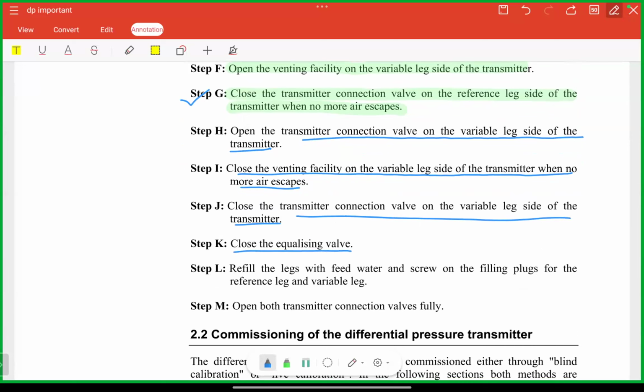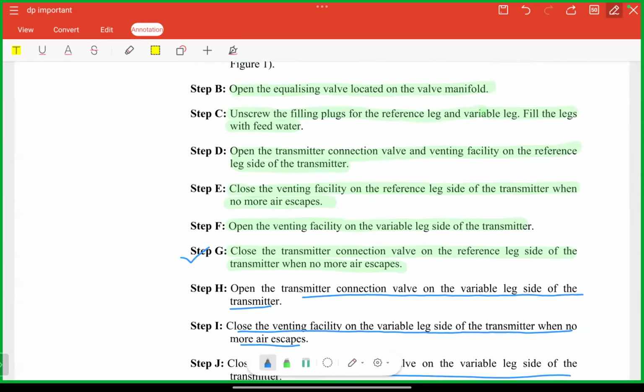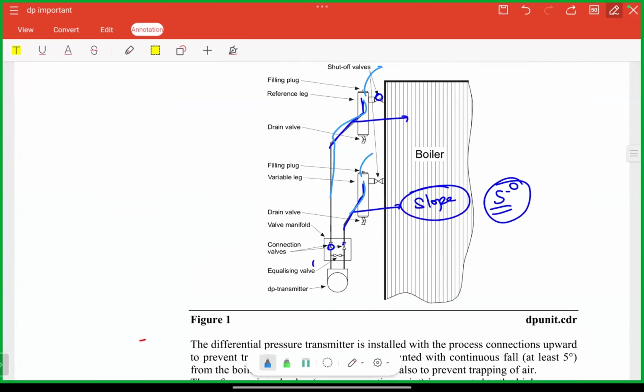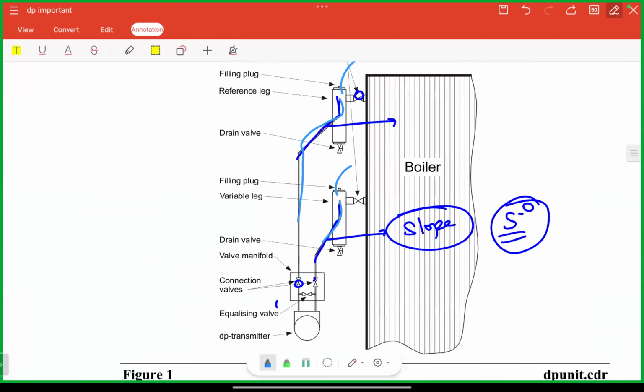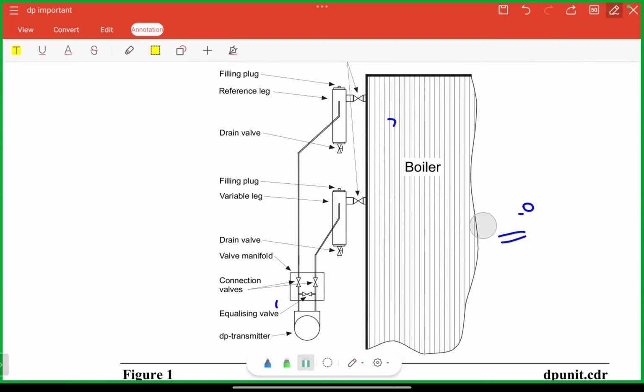Close the equalizing valve. Okay, and after closing the equalizing valve, refill the legs with the feed water and screw on the filling plugs for the reference leg and the variable leg. So during initial commissioning, simple understanding is that you are required to fill the water in the variable and reference legs and you are required to vent out the air.